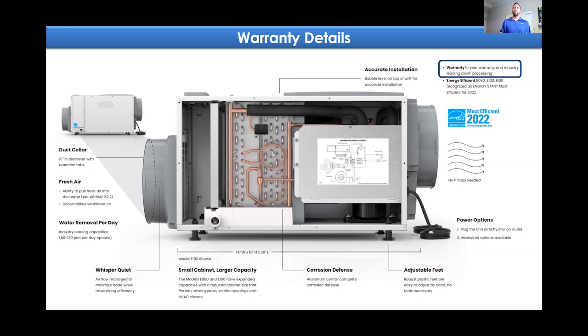The difference is we take your evaporator coil and piggyback it right on top of the condensing coil. So we're almost reheating that air, drying the air and then reheating it. We expand that air really quickly, and you get really good moisture removal and good dehumidification performance.